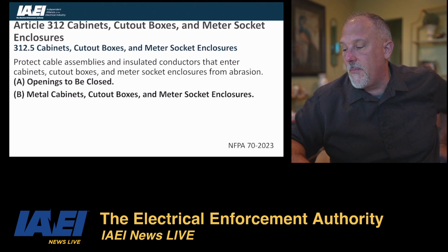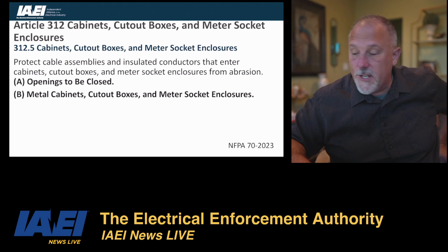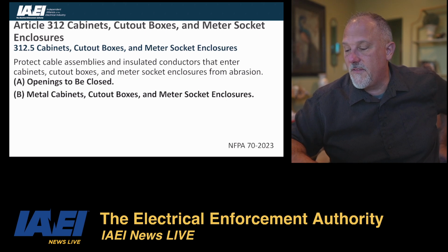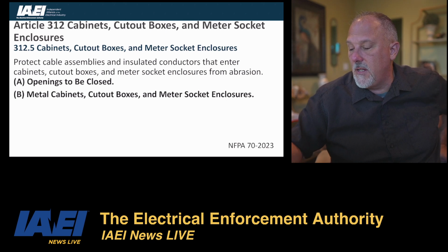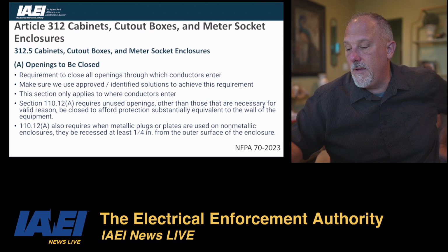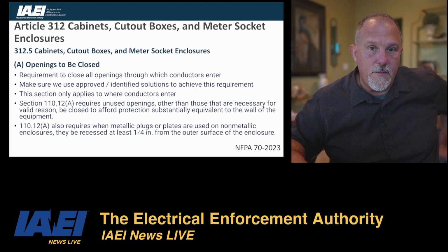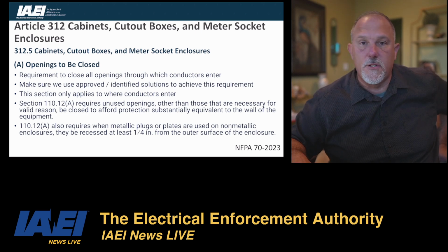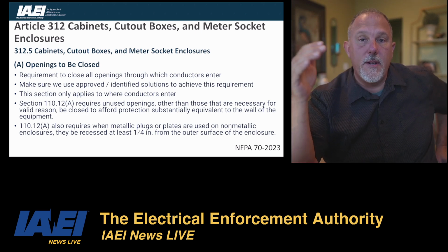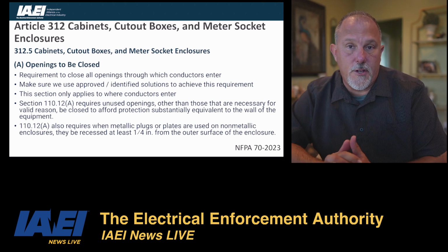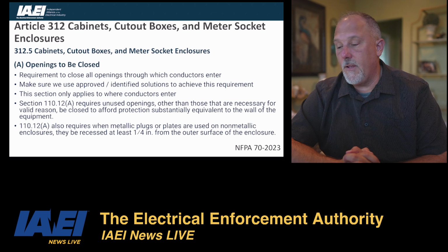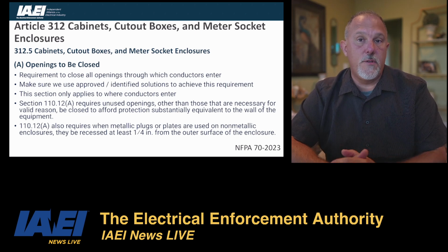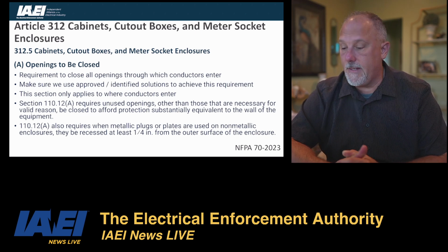So this is your 312.5: cabinets, cutout boxes, and meter socket enclosures must protect cable assemblies and insulated conductors that enter them from abrasion. Openings have to be closed, in metal cabinets, cutout boxes, and meter socket enclosures. So again, you have to close all of those gaps and holes. Make sure we use approved, identified solutions. You are probably going to come in on the top of that meter enclosure, and you can do that. You have to use listed components to get that done.